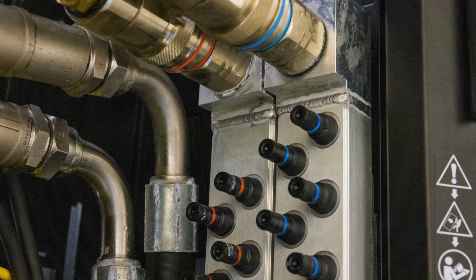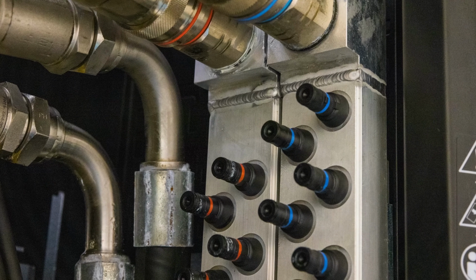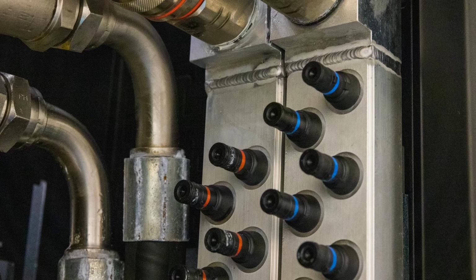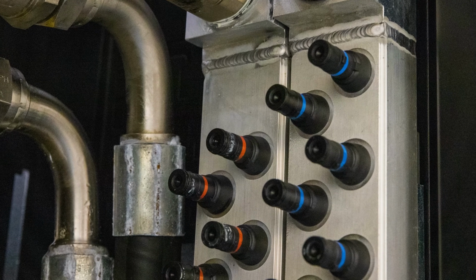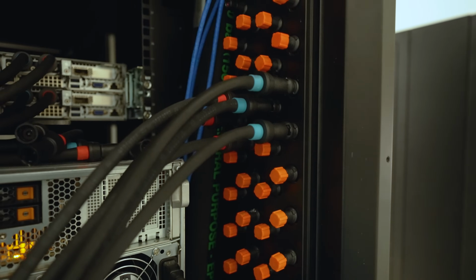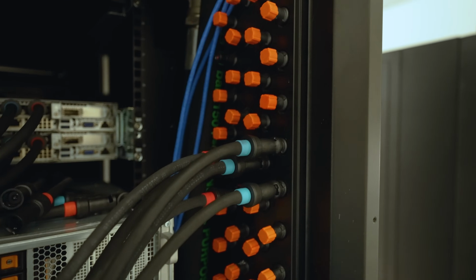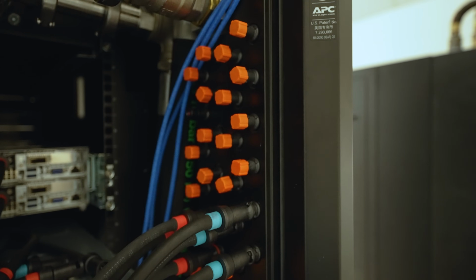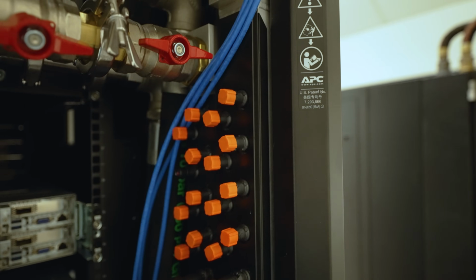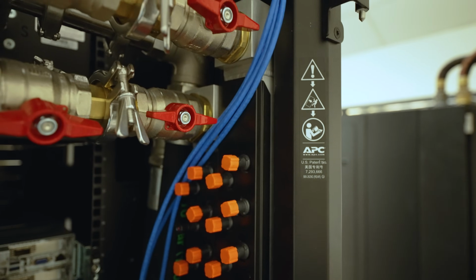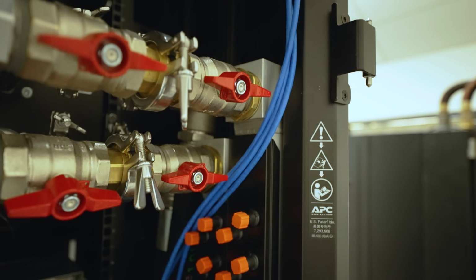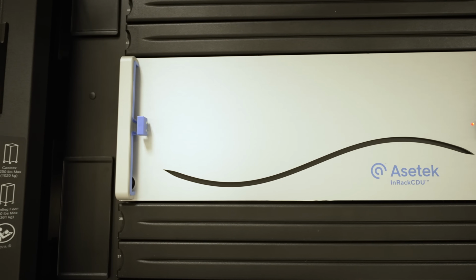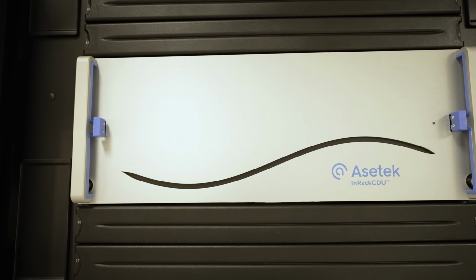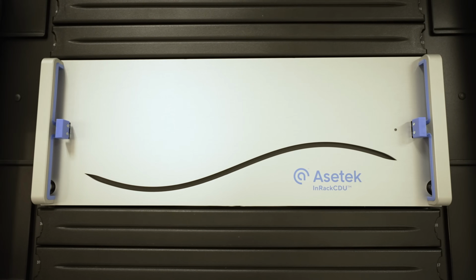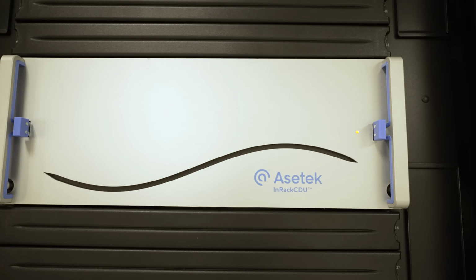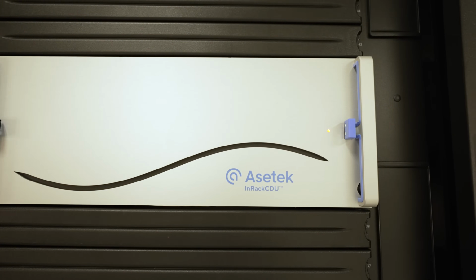And there are a couple of different ways that these basically work. Now, one way is that you could actually take facility water, pump it through your rack and then out. And the idea there is that a lot of times your water cost is less than your power cost, and so it's actually a pretty inexpensive way to go do that. The other way that you'll see is that you'll see some kind of heat exchange happen, and that could happen either in another rack or another part of the rack where you have a liquid to air and then that air goes out into the data center. The other way that you could do it is you could have a facility cooling solution or something like that. And so there are different ways that these are set up, but just kind of giving you an idea.